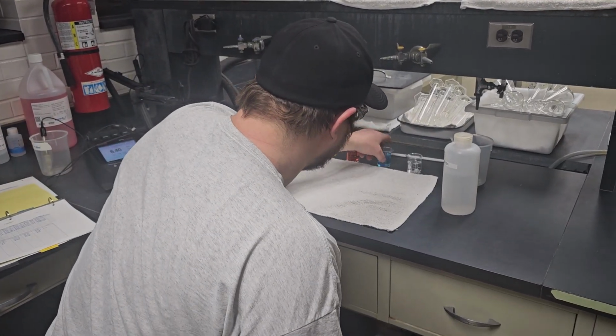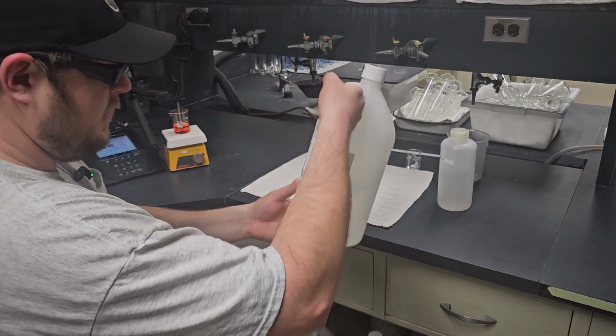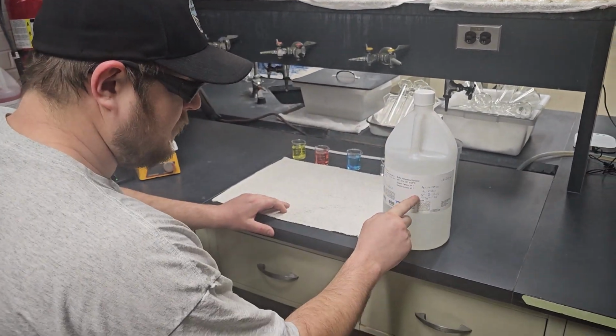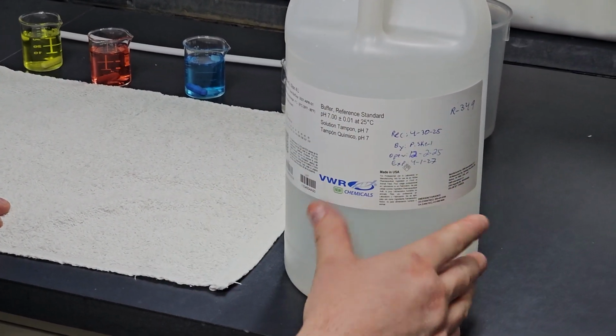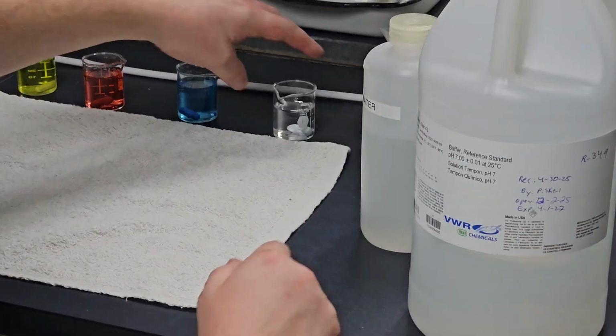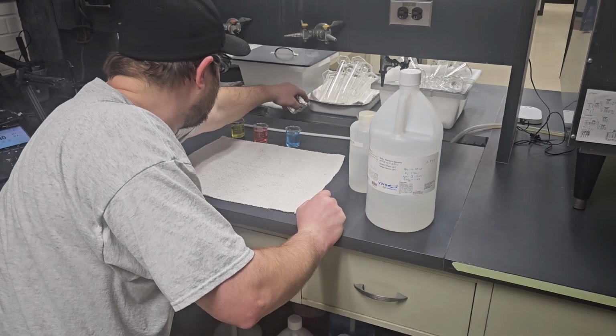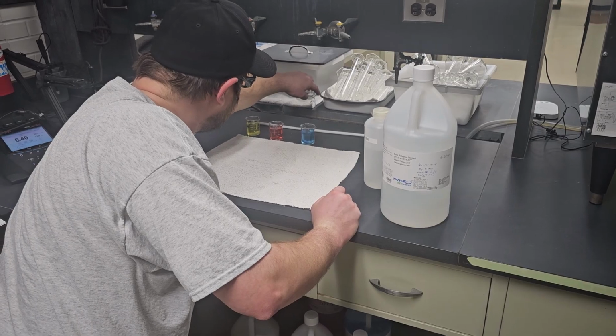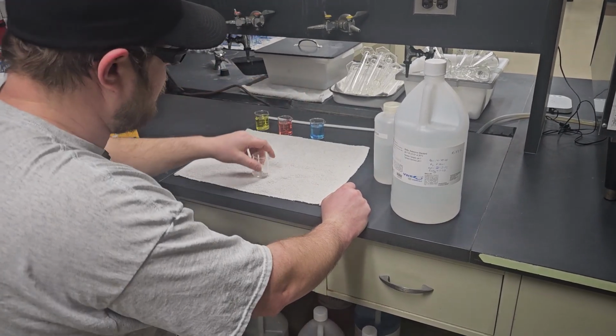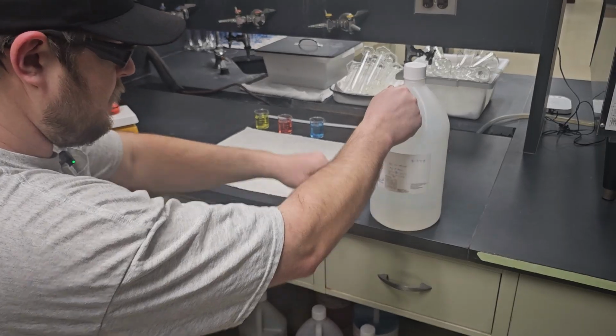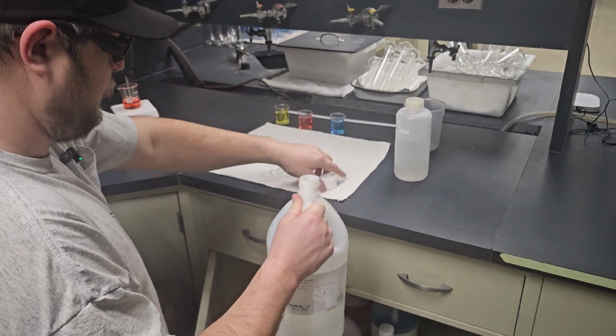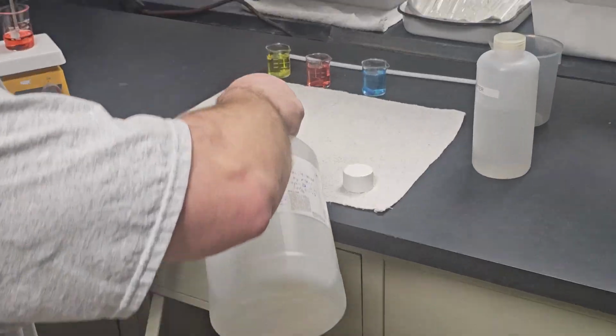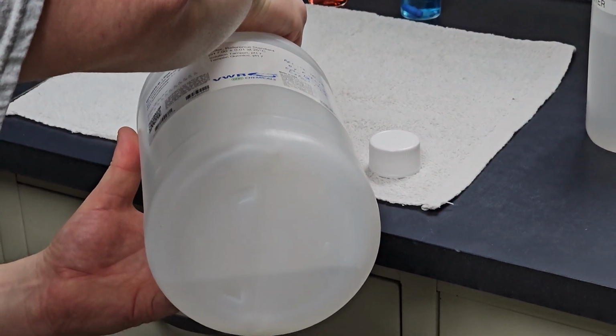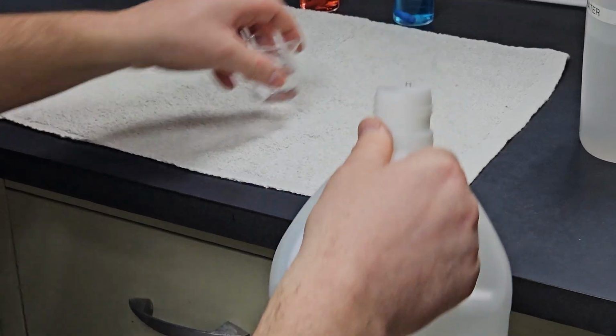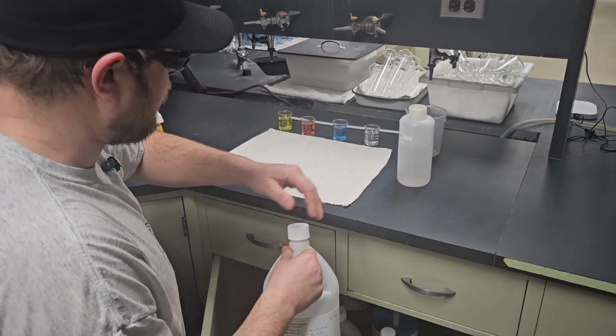And this is our quality control reference standard. It should be pretty much exactly 7. So this has got to be between 6.9 and 7.1. And we just read that at the end of our calibration to make sure that it took. And this expires 4/1/27. Okay, now we're ready to calibrate.